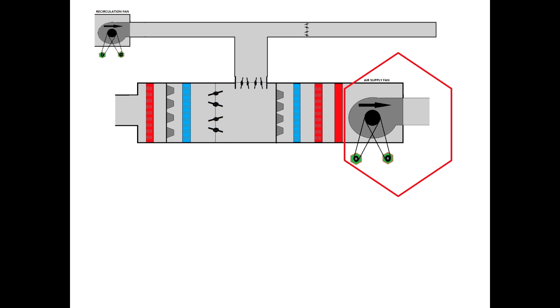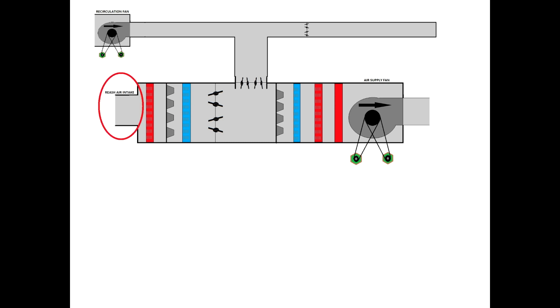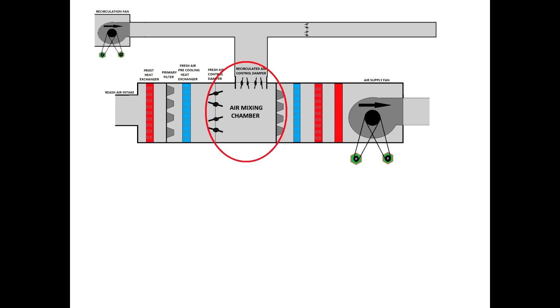So I'm sure you're familiar with the extract and supply fan. The one you see now surrounded is just a supply fan. This is the fresh air intake, and what you see now is the frost heat exchanger, the primary filter, the primary cooling coil. This is only for the fresh air intake, and this is the damper which allows more or less fresh air to come into the system. This is the recirculating damper which works against the fresh air damper, and this is the air mixing chamber where the recirculated and fresh air meet.